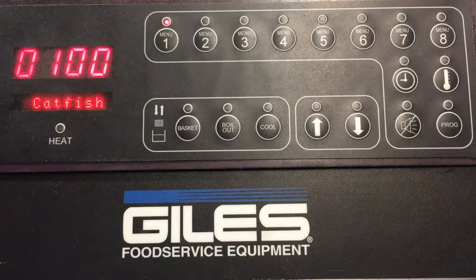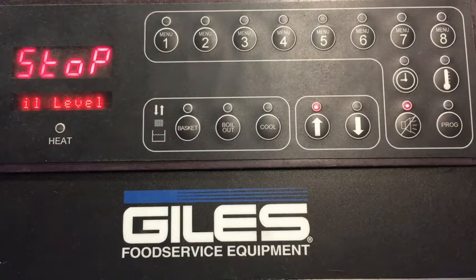Related to that element sensor, if they try to fire the unit up without enough oil on the element, you will exceed our max element temperature setting, which is typically 580 to 600 degrees. If that happens, you're going to get an ER11 message, which is going to shut your heating down, and then it'll go into an alarm and shut the heating down. Again, stop, ER11, oil level, max element temp, everything shuts off. You can silence the alarm, but you cannot do anything else.